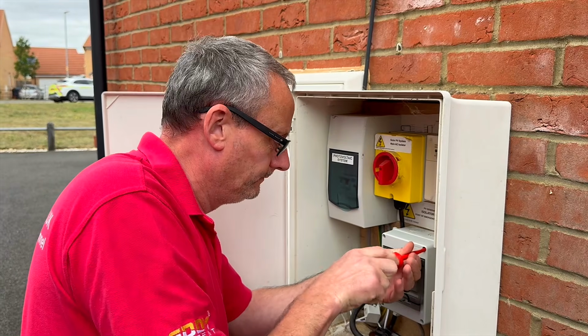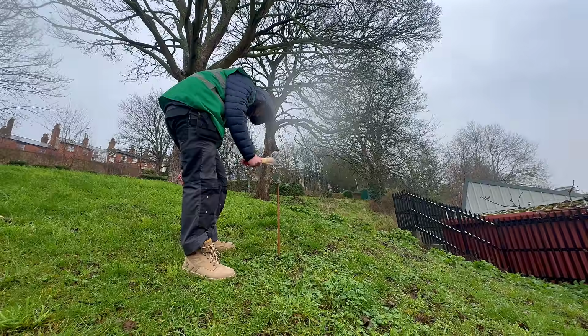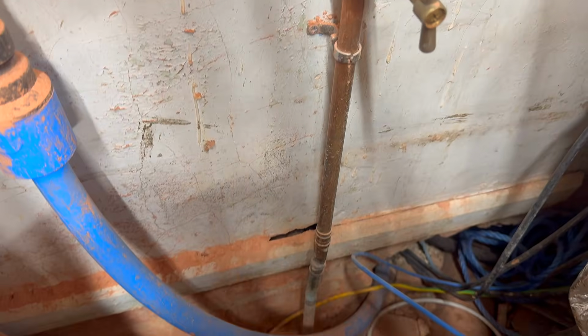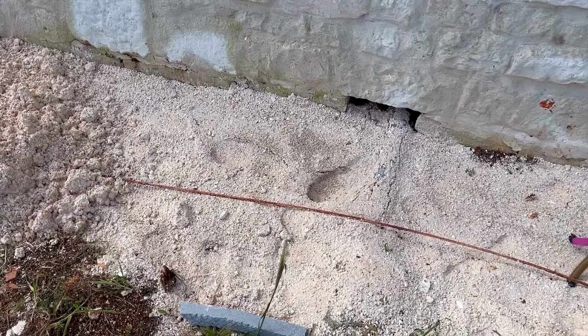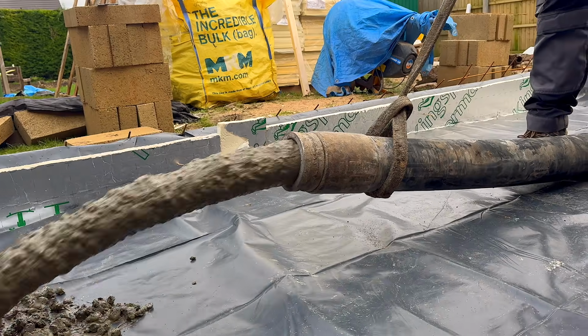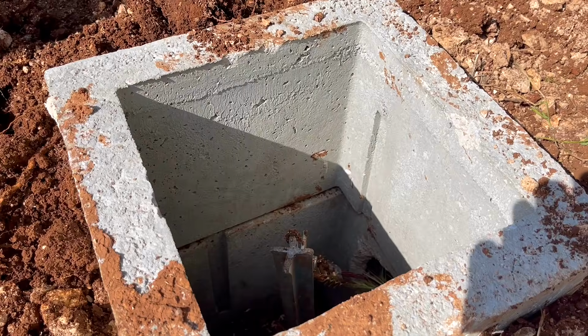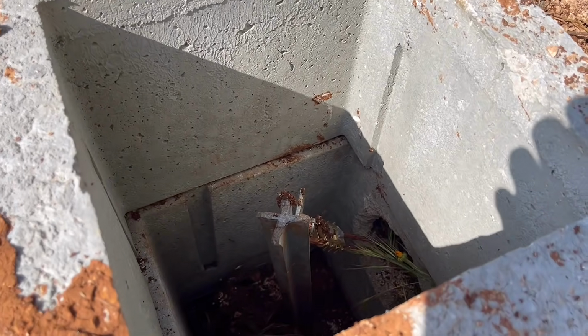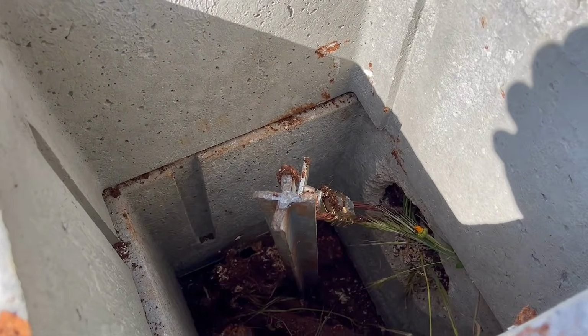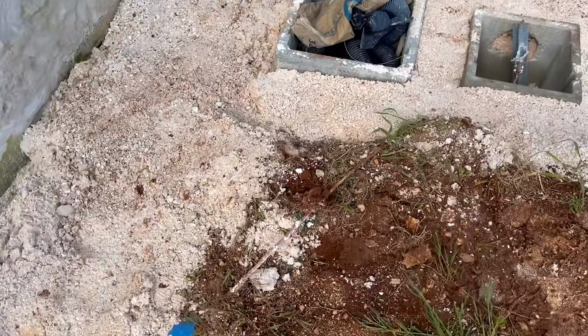So when people hear the term earth electrode, they may picture a metal rod driven into the ground. But it's not the only form an earth electrode can take. Historically, water pipes have been used, structural steel has been used, copper tape, buried mesh, foundation earthing systems. All of these are forms of earth electrodes. The common factor is not the shape of the material, it is the contact that it makes with earth, because an earth electrode is only as effective as the ground that it's connected to, and that's why we need to test it.